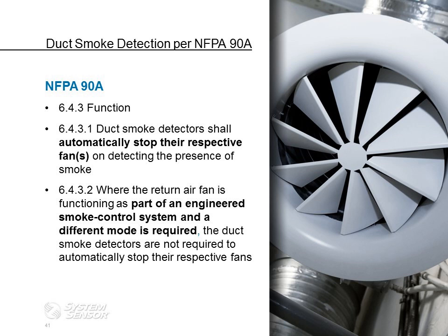If you are in a building that they are doing a smoke control system, even if there is a duct detector, that duct detector, while it activates, may not be required to shut off an air handler or shut off a fan. It may be designed in that engineered system to actually turn on an exhaust fan to draw smoke out of the building. So just be aware of that.